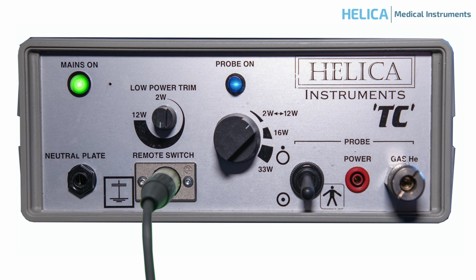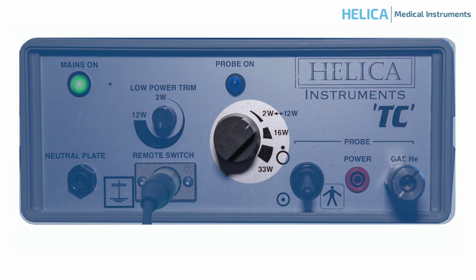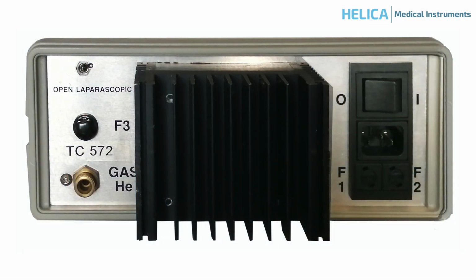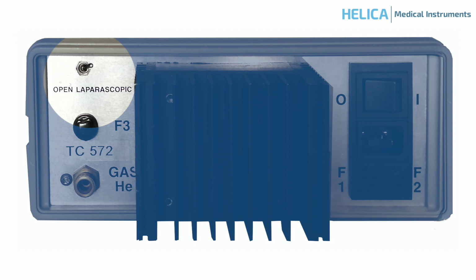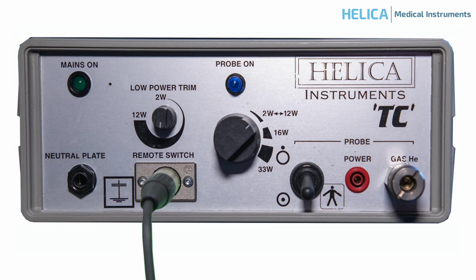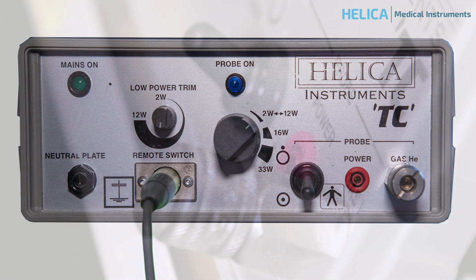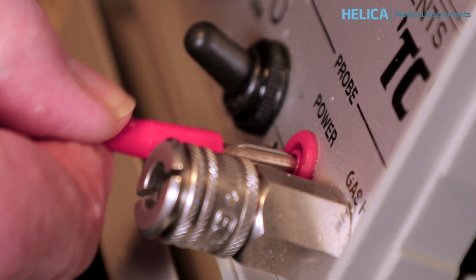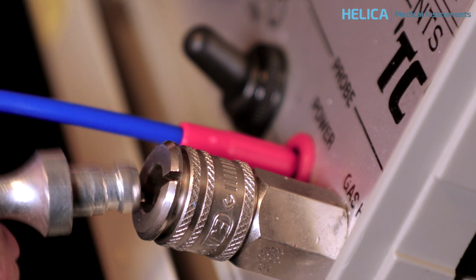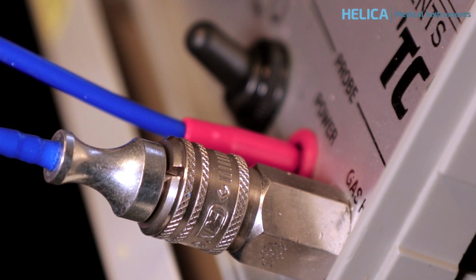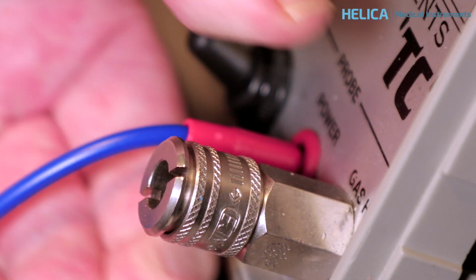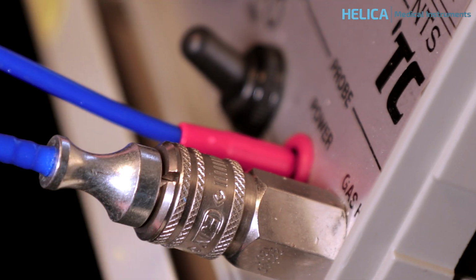A blue light and an audible buzzer indicate when the foot pedal is depressed and the device is active. The main power control knob should be in the low position, and the procedure switch at the back of the machine should be switched to laparoscopic mode. Attach the probe to the Helica by means of the 2 connections on the front right of the device. The power lead is a push fit, and the gas lead clicks into position with the retainer. To remove the gas lead, push it in again and this will release the cable from the socket.